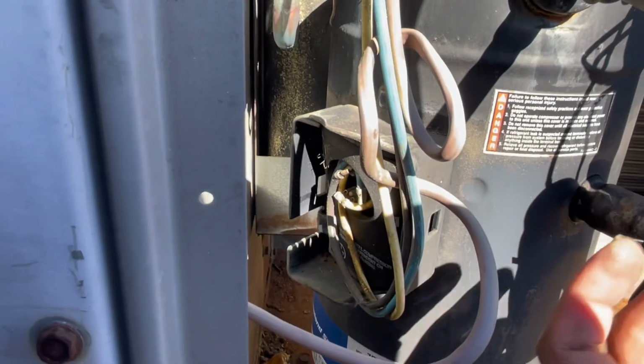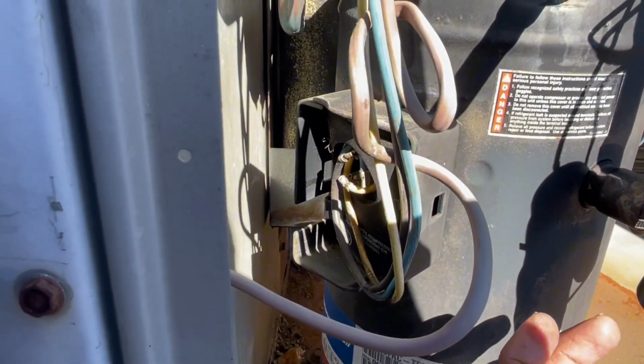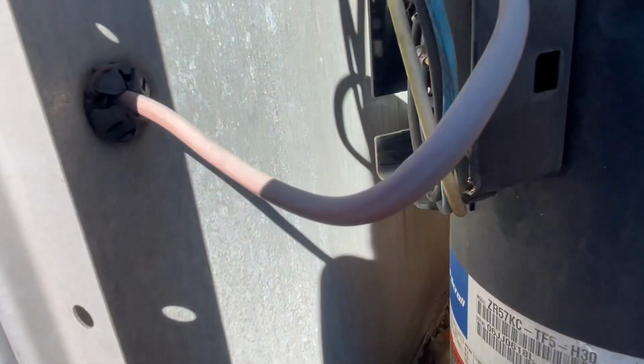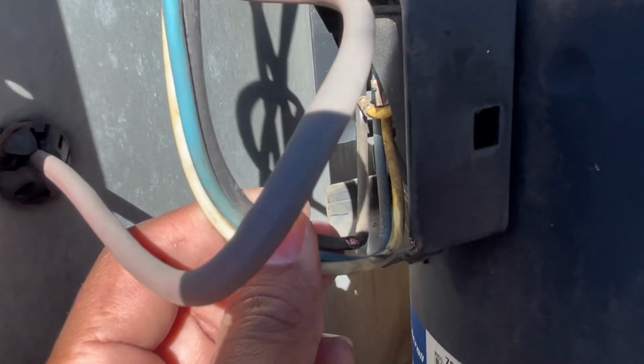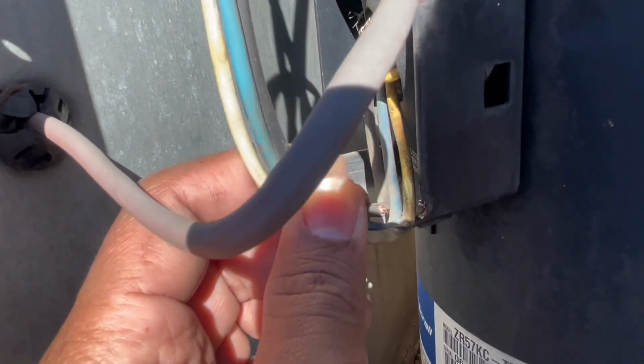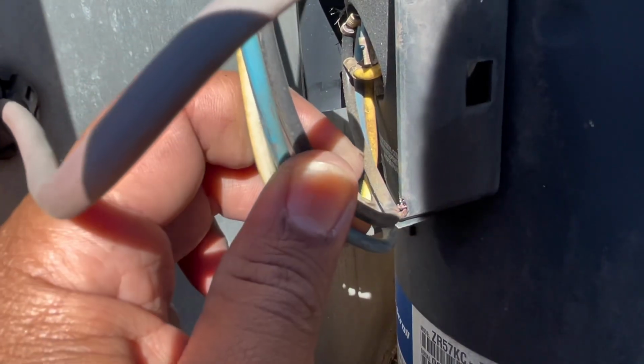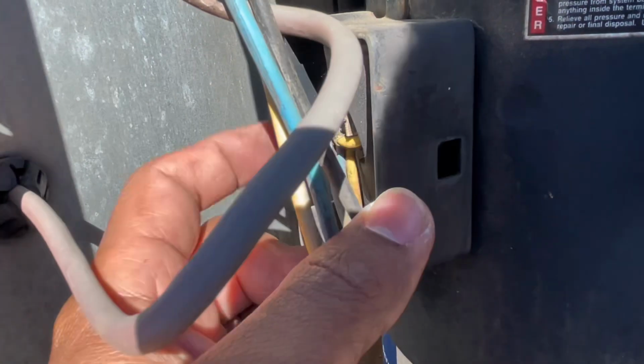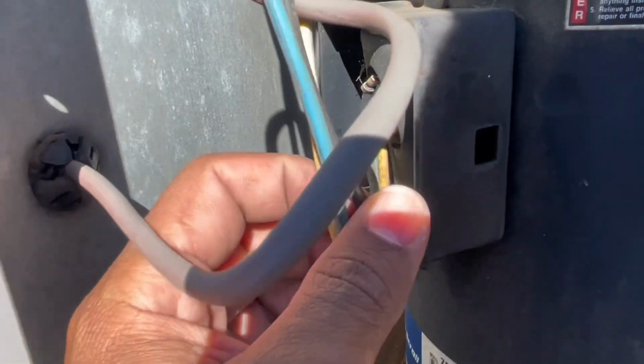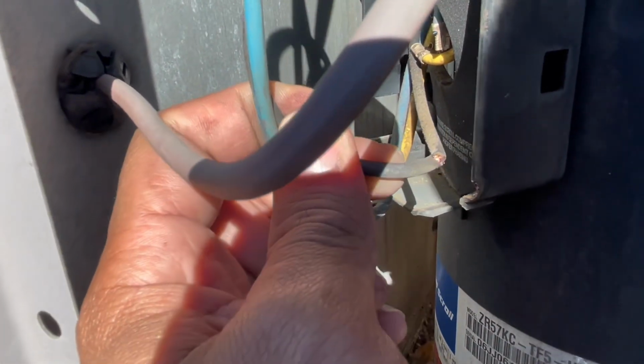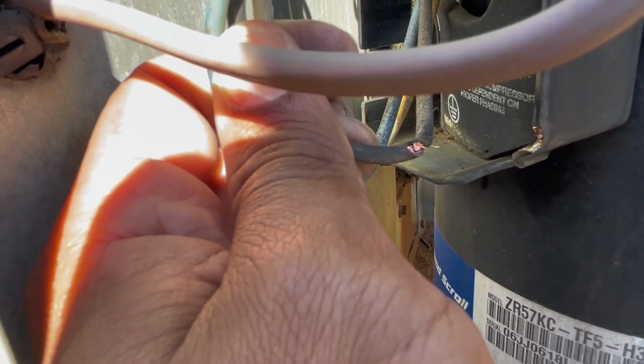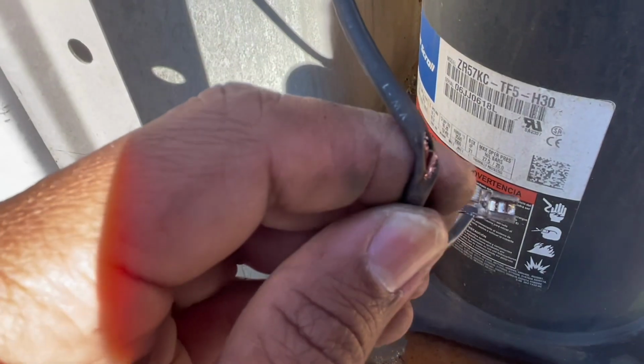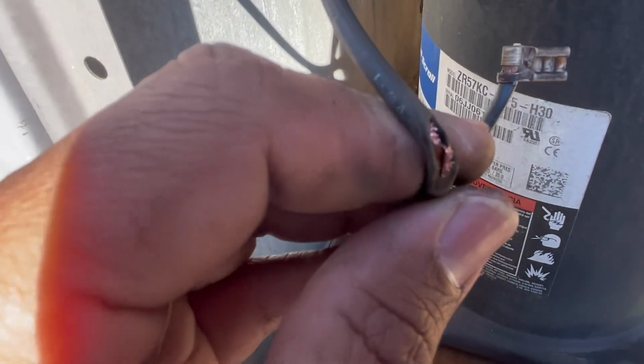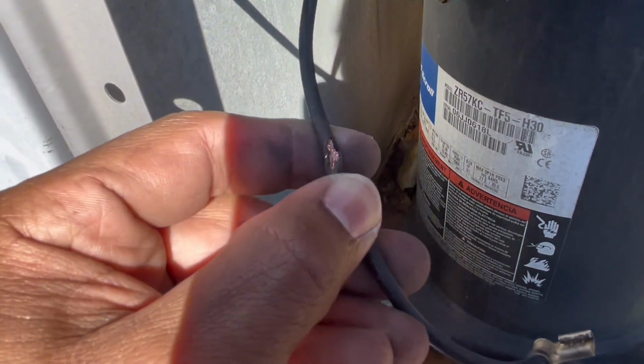Okay, as you guys can see right here, everything looks good until you check this part right here, which is the black wire that was making contact with this cover, which is a metallic cover, and this was causing a short, and that's probably the reason that triggers that breaker down there. Wow, this wire looks really bad. So now let's fix it.